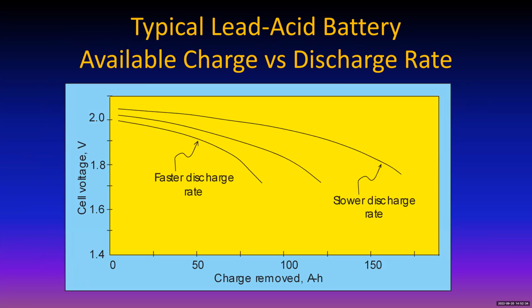Here's an example with lead acid batteries. If you discharge them slowly, you can get a whole lot more ampere hours, which is basically the energy, than if you discharge them quickly. And again, it's simply because in the fast discharge, your ampere hours get dumped into heating the battery, whereas with the slower ones, they actually get the current out of there and it does work outside the battery.